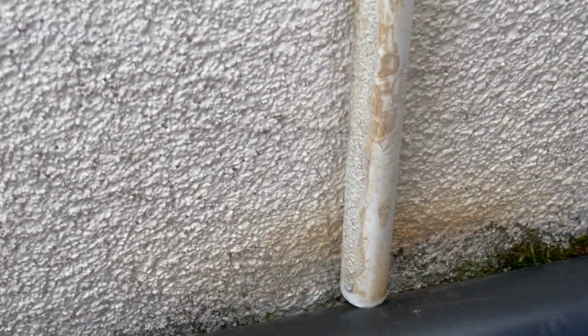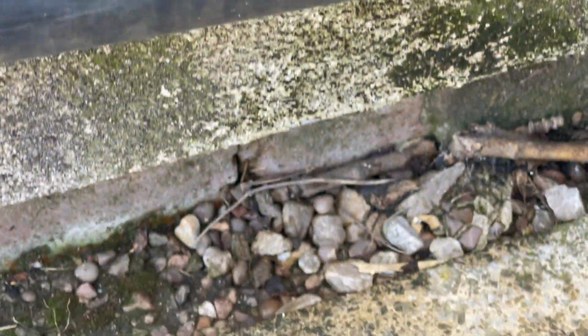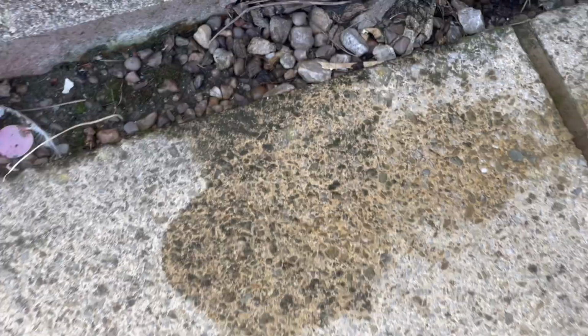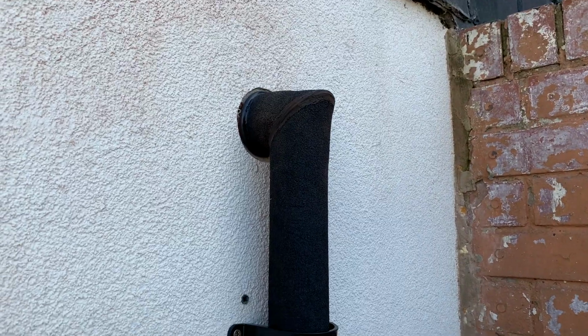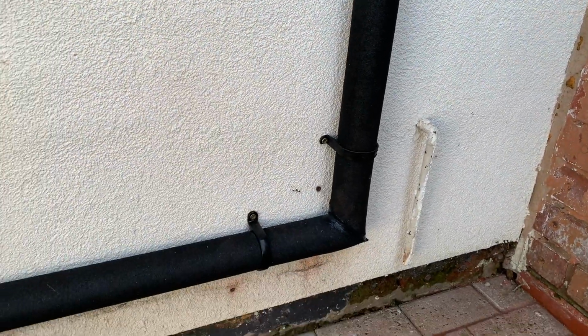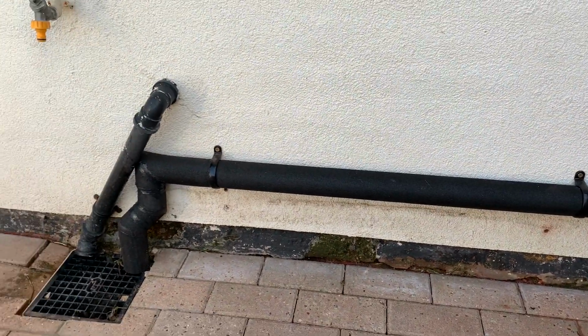Now, another common cause of boiler breakdown is incorrectly installed condensate pipes. So this condensate pipe is not installed correctly and is likely to freeze in winter. So if you don't want a frozen condensate pipe in winter and boiler breakdowns, then make sure your condensate pipe is insulated. Now, these are the main things we should be looking at to make sure that these boilers are going to definitely last at least 15 years of age.